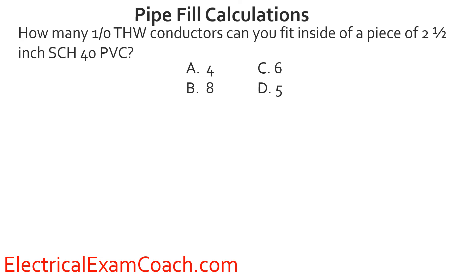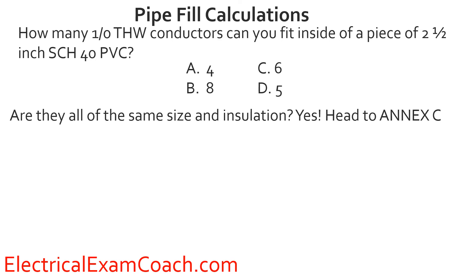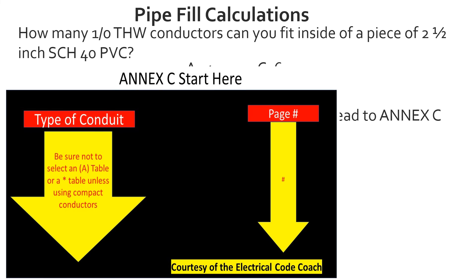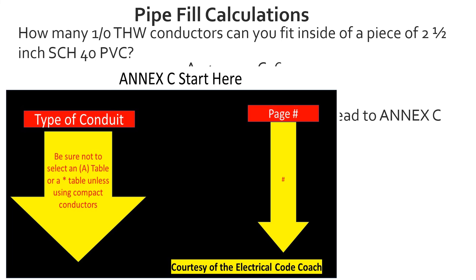Practice problem: How many 1/0 THW conductors can you fit inside a piece of 2.5-inch schedule 40 PVC? Are they all the same size and insulation? Yes. Head to Annex C, find schedule 40 PVC — not the A version — cross to the page number, read the black bold heading to confirm the right table. Find THW insulation, find 1/0 wire size, come across the top to 2.5-inch conduit, tee off, and the answer is 8 conductors.